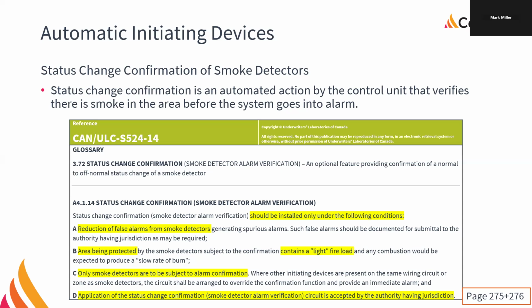And so we're doing the upgrades to the system and all this. And we replaced the system and everything went back in on status change confirmation because the drawings said that we are to match the existing programming, right? So that got reconfigured. As part of the upgrades and everything that was being done to the building, the maternity ward was closed down for 6 weeks because we had to completely redo the maternity ward because it was terrifying how outdated some of that stuff was. And then it got reopened, and as part of the reopening, the configuration of the ward had changed. Things had been moved around and all this, and so they had staff training.